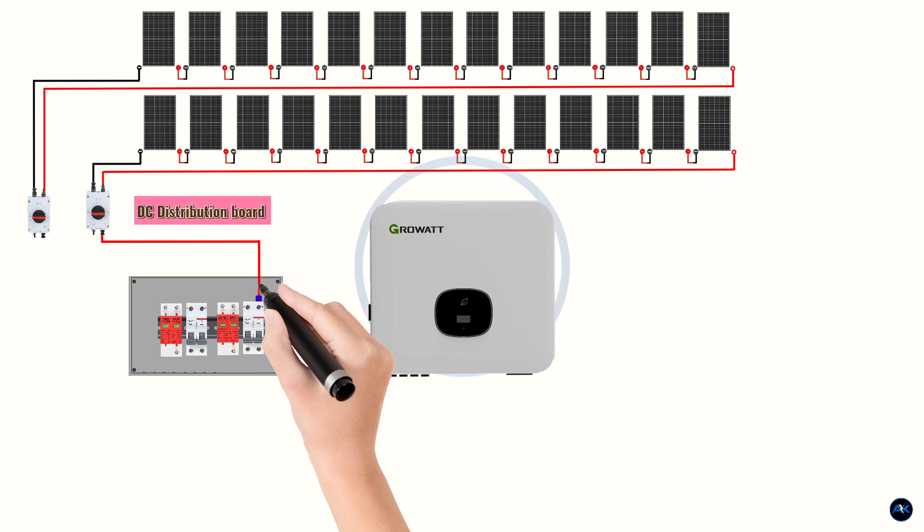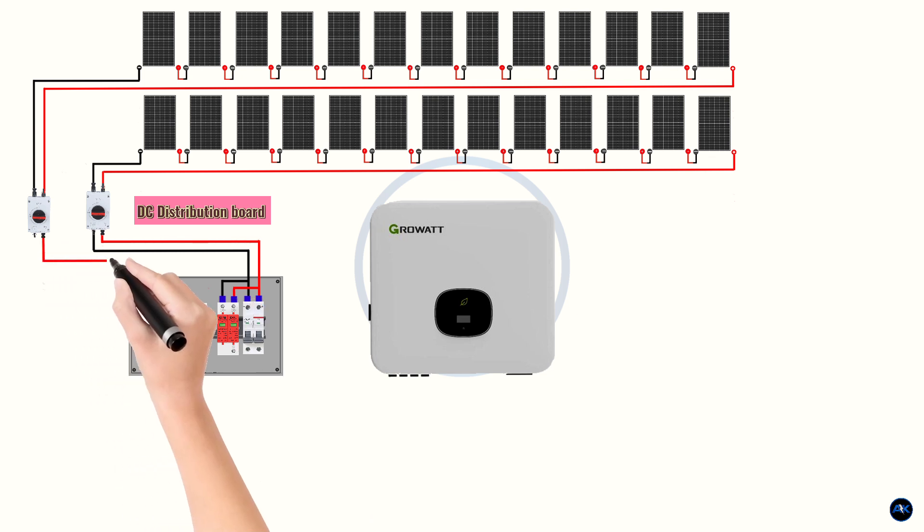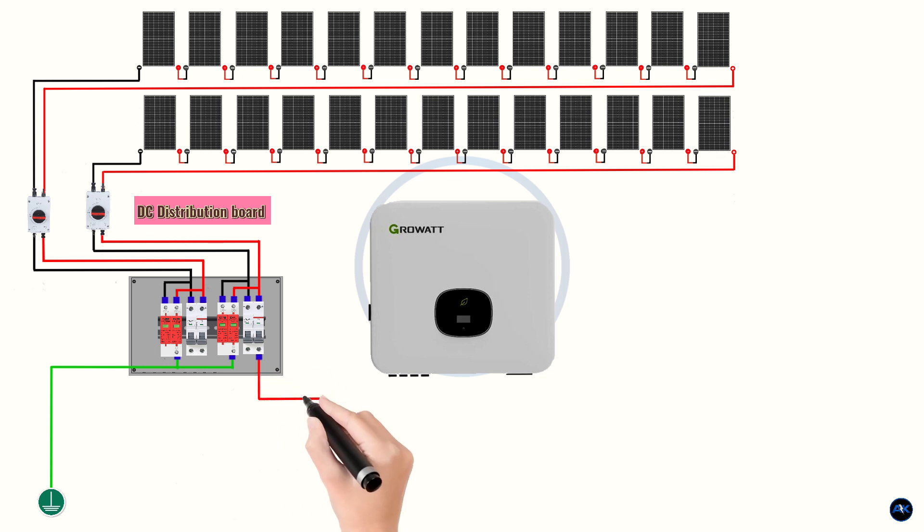Isolator switch to MCB connection: connect the positive output of the isolator switch to the positive input of the DC MCB. Connect the negative output of the isolator switch to the negative input of the DC MCB. SPD connection parallel to MCB. Positive connection: connect a wire from the positive output terminal of the MCB to the positive terminal of the SPD. Negative connection: connect the wires from the negative output terminal of the MCB to the negative terminal of the SPD. If the SPD has a common negative, connect it to the negative output of the MCB. Earth connection: connect the earth terminal of the SPD to the grounding system, earth bar, or designated grounding point. MCB output to inverter: connect the positive output of the MCB to the positive PV input of the solar inverter. Connect the negative output of the MCB to the negative PV input of the solar inverter.